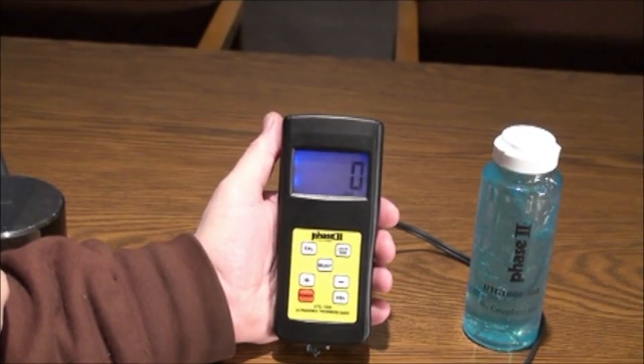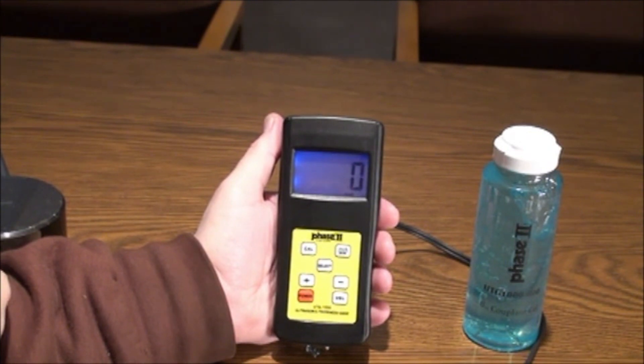This is an instructional video detailing the applications and functions of the Phase II UTG-1500 ultrasonic thickness gauge. The UTG-1500 is designed to test metallic and non-metallic materials, as long as they have parallel top and bottom surfaces and sound waves can travel through the material.